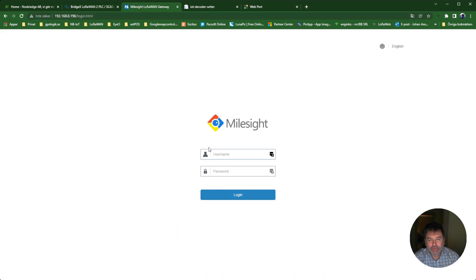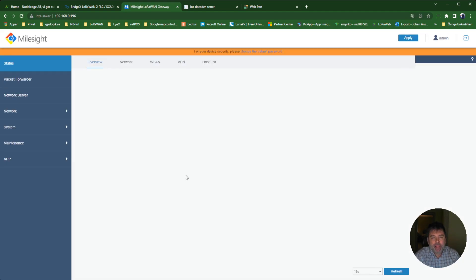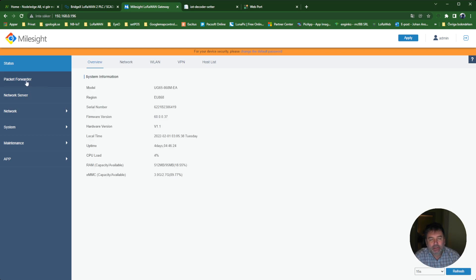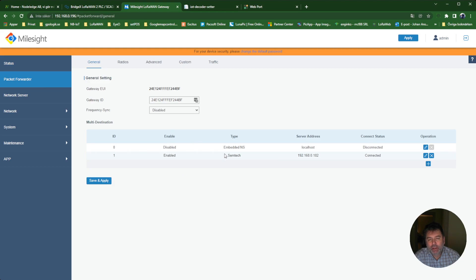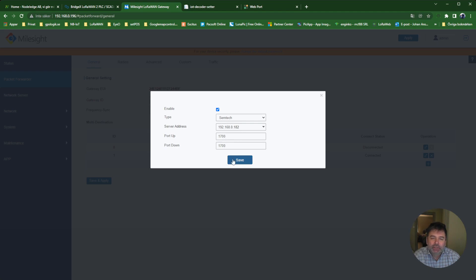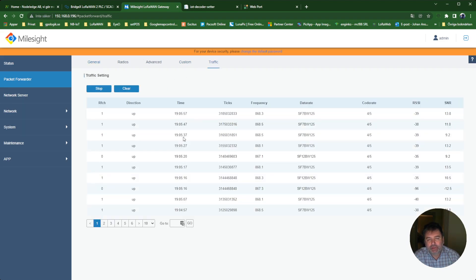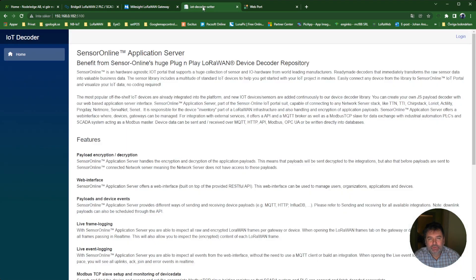First, you log in to the Milesight web interface. In the menu here you go to Packet Forwarder and make sure that your gateway is running in packet forwarder mode to the IP number of the BridgeX on port 1700. Now there is traffic here from the ELSYS sensors, and it's being forwarded to the decoder.